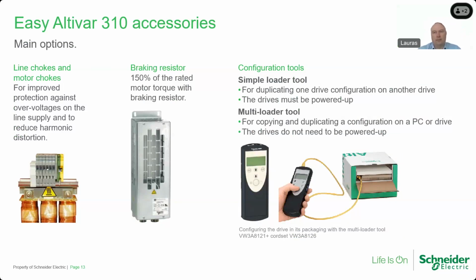Regarding configuration, as it is a simplified product, it does not support DTM, so you cannot make the setup using the software. There are several options. You can do a manual setup using the display and buttons on the drive. Also, machine builders usually use the same application for the same machine, so they need to just copy and paste the same application.